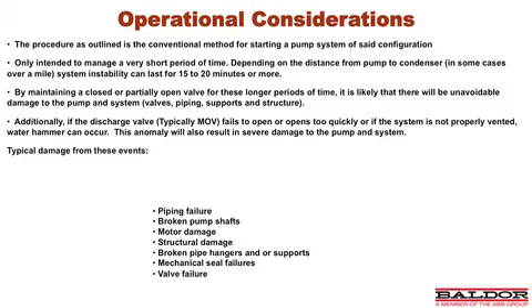So in this diagram, the operating considerations in a circ water pumping application, as we outlined, are the conventional flow process and startup methodology. During the startup sequence, the pump is started against a closed discharge valve. As the pump is energized, the discharge valve slowly opens. During this sequencing, the pump goes through a very abnormal cycle.